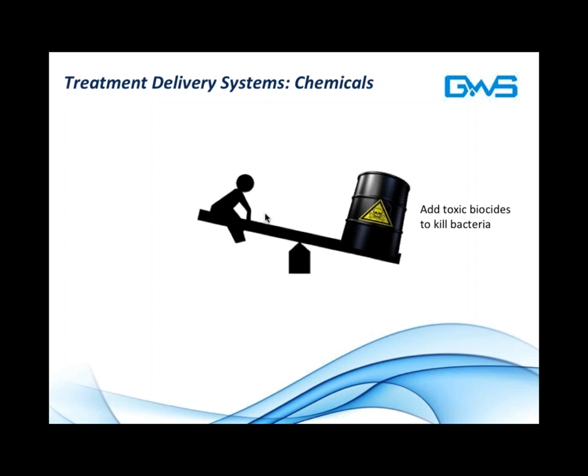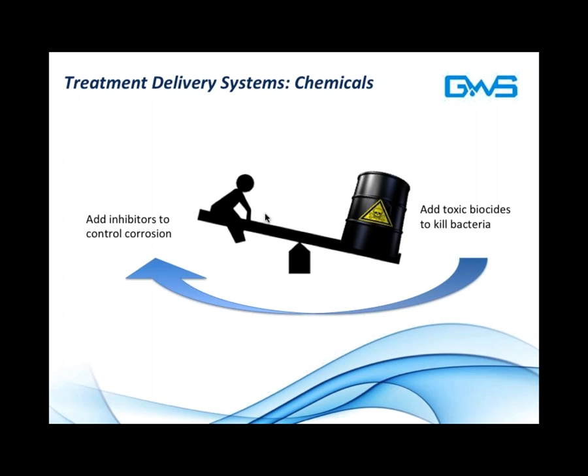In this case, with a cooling tower using chemicals, toxic biocides are often added to kill the bacteria. That's important because, of course, the risk of Legionella is real. And without biocides, water will breed life. There's just no question about that. Biological results can be quickly ascertained with a simple dip slide test or other more complicated lab tests. That's something that most operators are very sensitive to. The problem is that toxic biocides are usually oxidizing in nature, and they're very caustic for cooling towers.